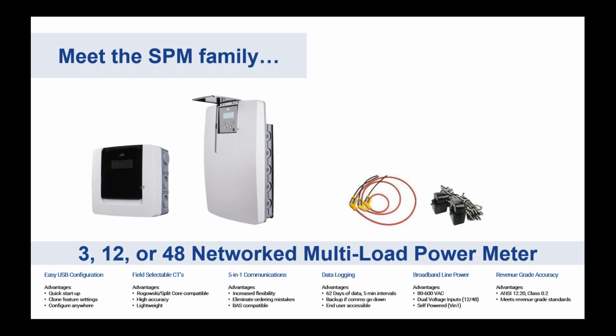The meter will also solve that age-old problem of data logging and backing up your data. So if your comms ever go down, you have a backup of that energy data that you can download from the meter and see what happened while the comms were down. So if the comms went down Friday night and no one noticed till Monday, you'd be able to gather that energy and power information that occurred over that weekend.